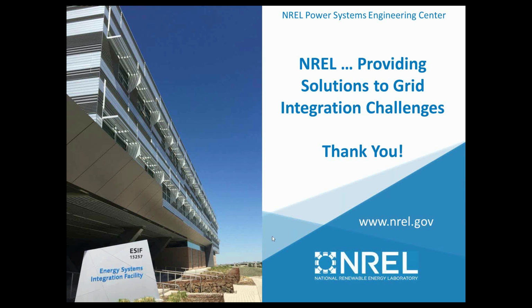Next. Okay. What are the trade-offs between trying to meet compliance for under frequency load shedding and having frequency points that do not adversely impact a potential unintentional island? Well, obviously, this is something that really needs to be looked at. It depends where you have your under frequency load shedding set points. Typically, those are going to be pretty low, 59.5 hertz or something. It could be different depending on your situation. But you probably do not want your DG trip points to be tripping below your under-frequency load shedding trip points. So you still want your DGs to be online.